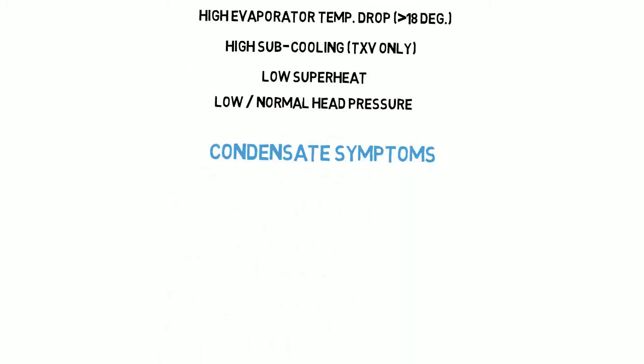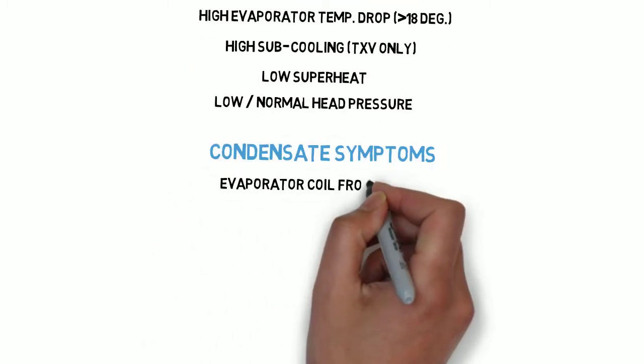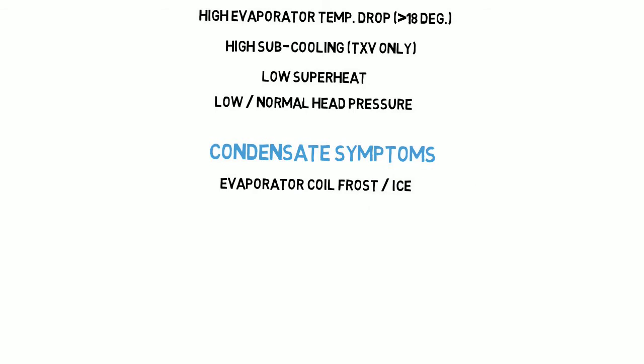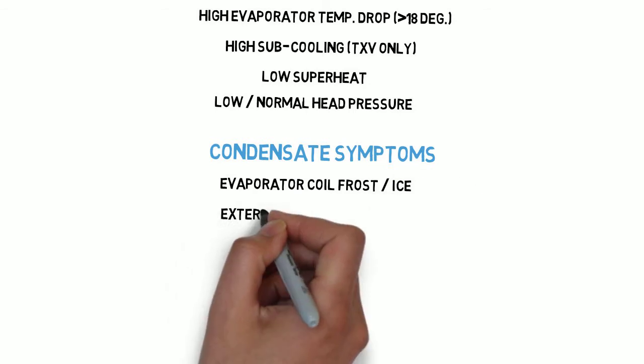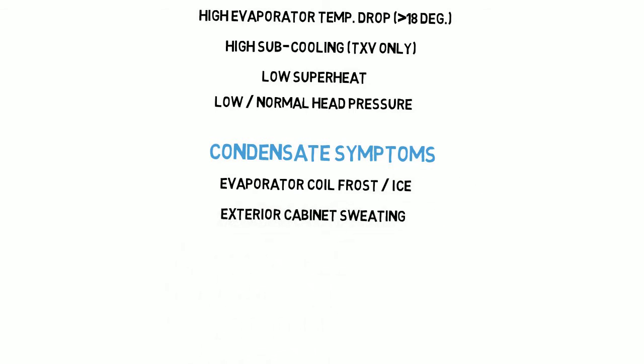Condensate symptoms of low air flow: ice and frost on evaporator coils, and cabinet sweating.